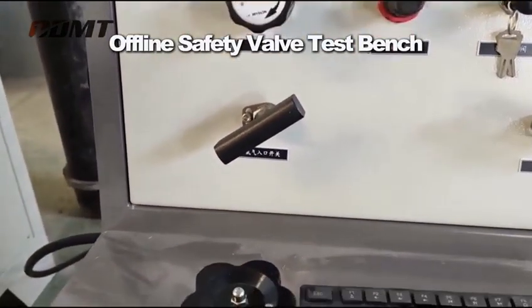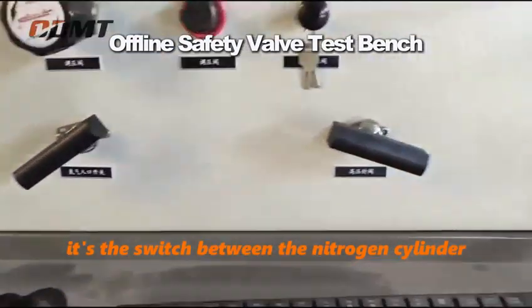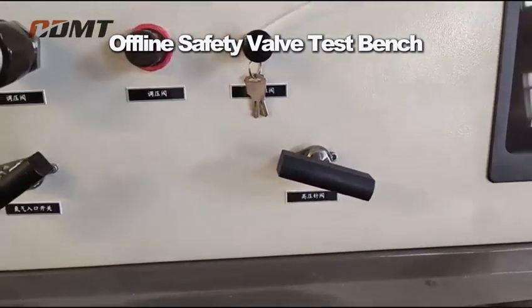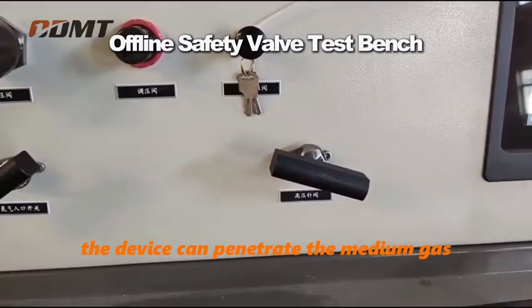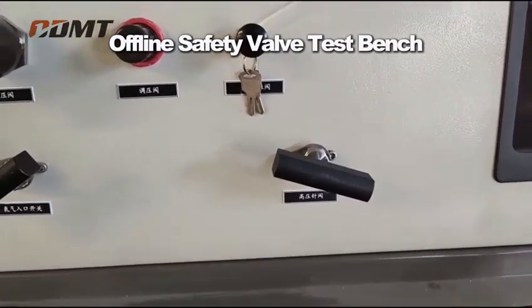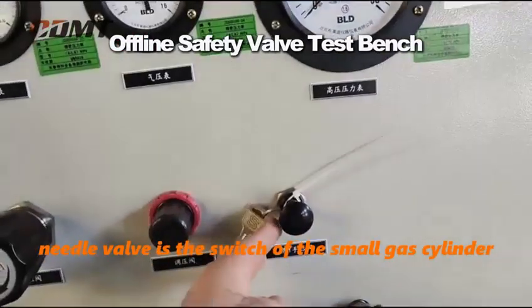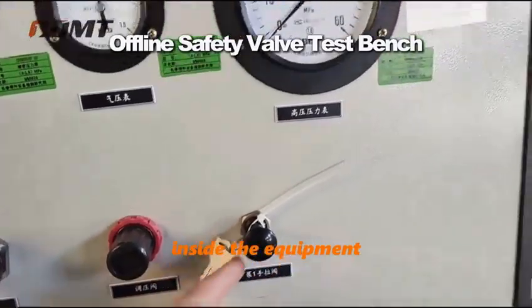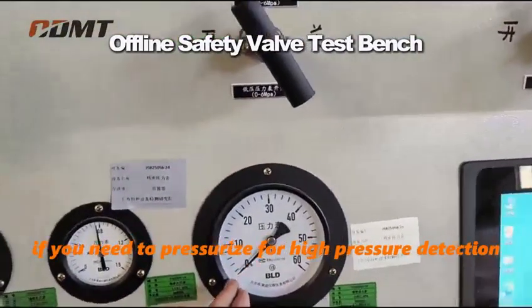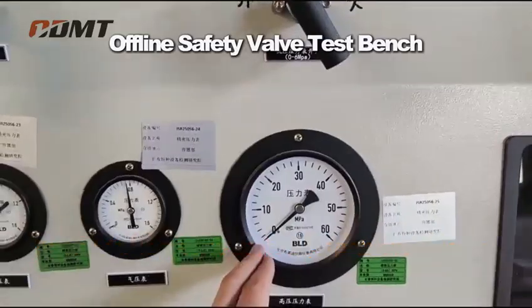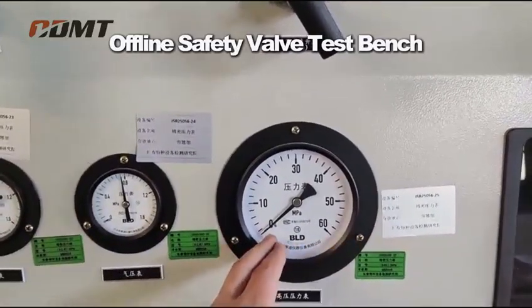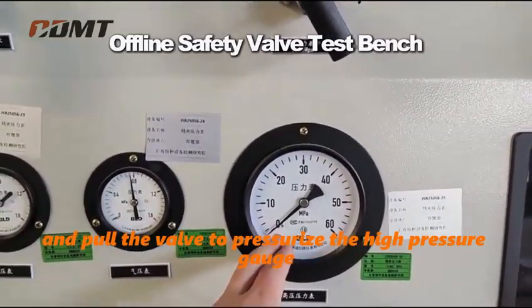The nitrogen inlet switch is the switch between the nitrogen cylinder and the device. Turn it on before the device can take in the medium gas source. The high-pressure needle valve is the switch of the small gas cylinder inside the equipment. If you need to pressurize for high-pressure detection, you need to open it. Then pull up the pump and pull the valve to pressurize.